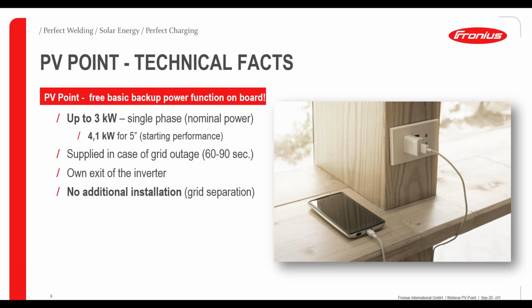In case of a grid outage, there is an interruption of the supply for about 60 to 90 seconds, different on the different inverters. On the Symo range, it's about 90 seconds at the moment. The power supply will then start automatically again on this socket.